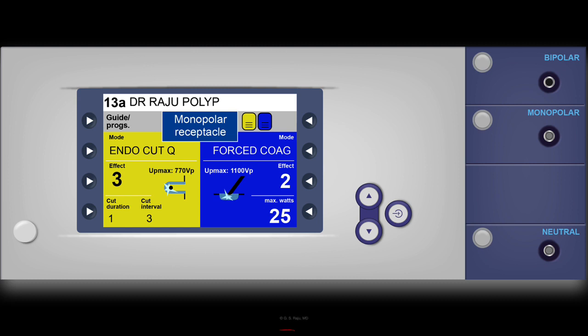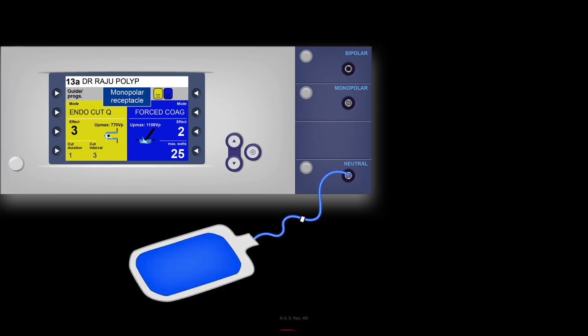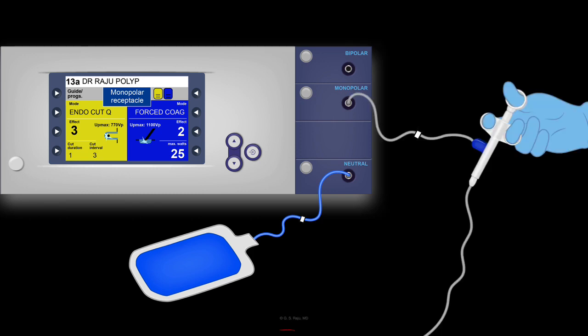So let us look at it. Okay, here is my electrosurgical generator. I set up the program. On the right side, you have 3 sockets, a bipolar socket, monopolar socket, and a neutral socket for the returning electrode from the dispersive pad. So, first attach the dispersive pad to the neutral socket, electrode socket, and then attach the snare to the monopolar socket. So we have now the circuit ready to be activated.